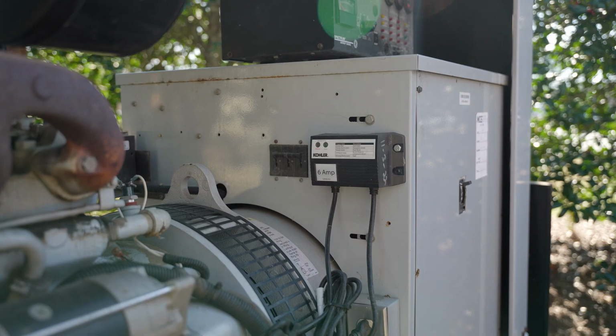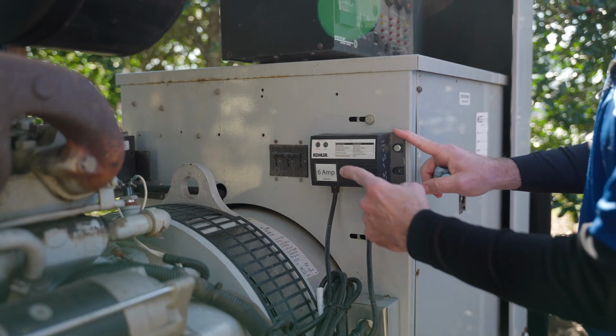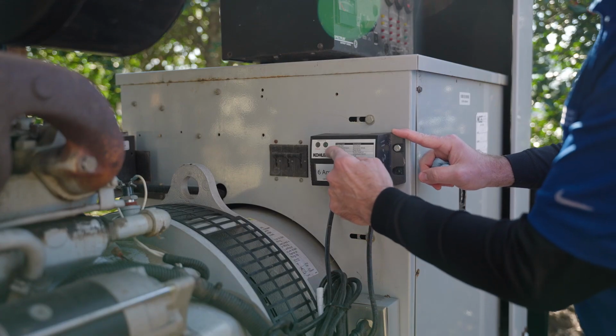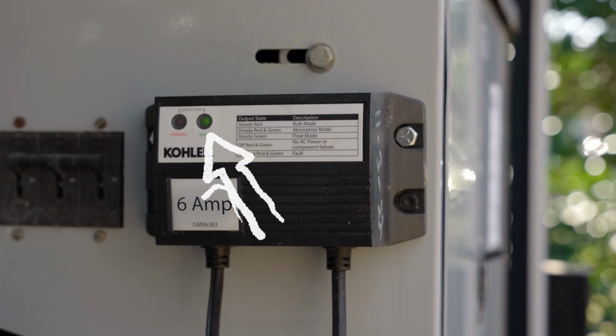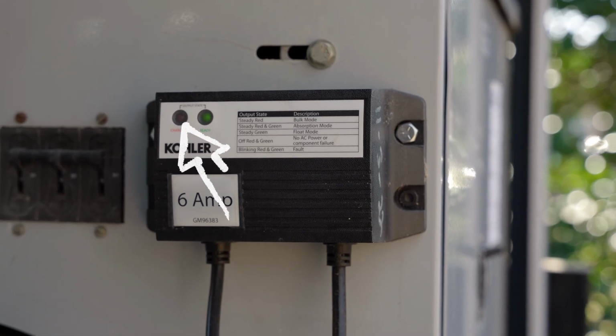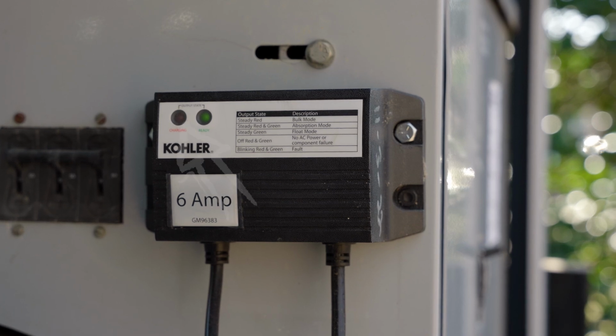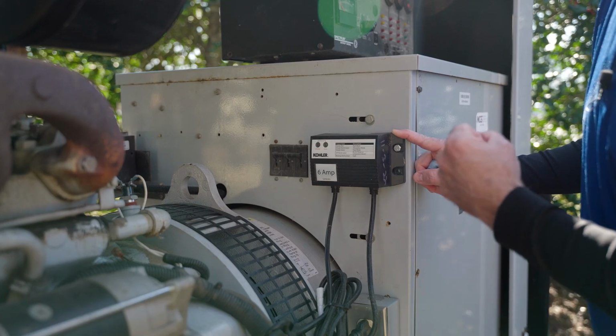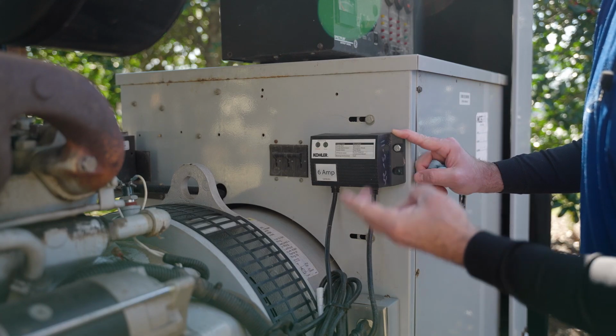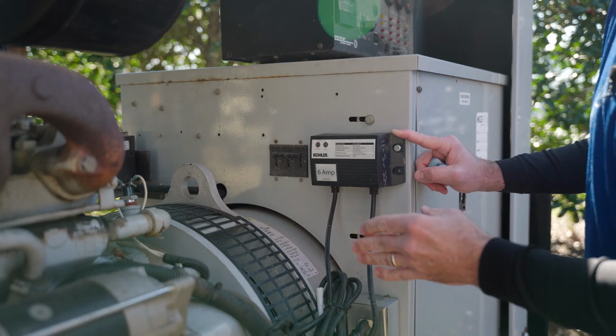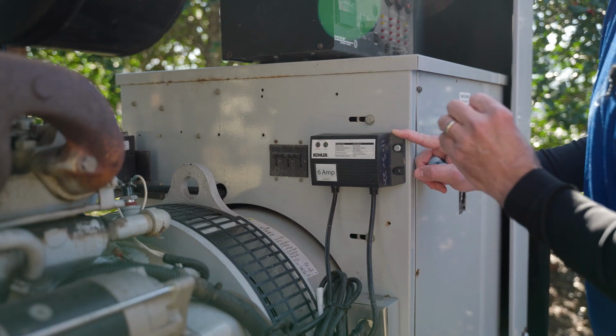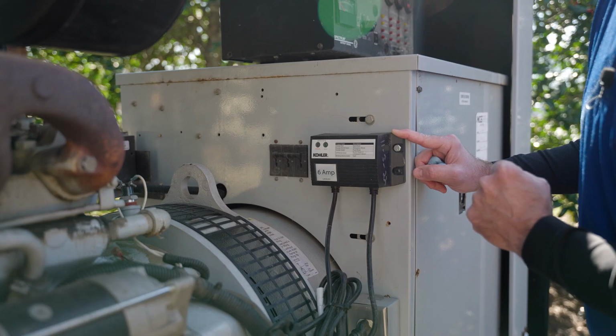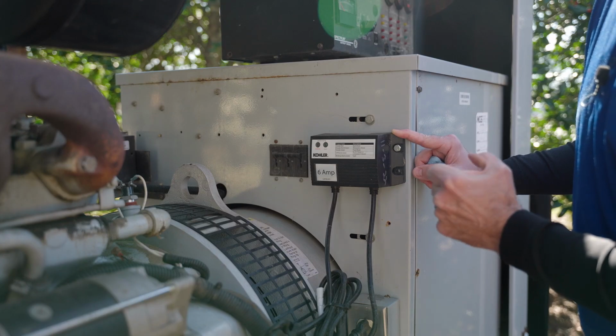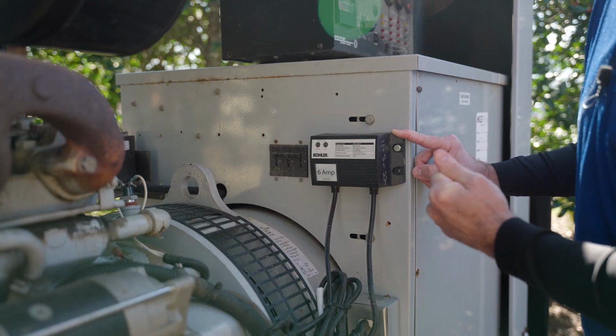The last item that we need to check before starting the generator is to check the battery charger. The battery charger has two lights on it. It has a green light letting you know that the charger is ready, and then it has a red light for charging mode to charge the battery. You should always have at least one light, if not both. If you have no lights, that means the charger is not putting out charging to the engine starting battery, and it may cause an issue or not allow the generator to start.